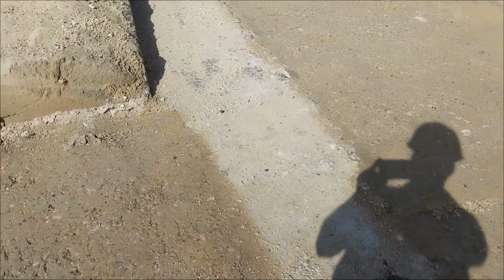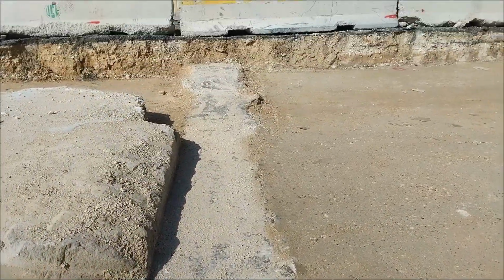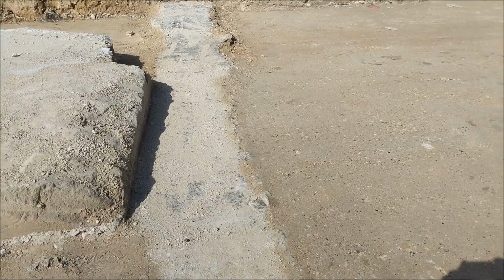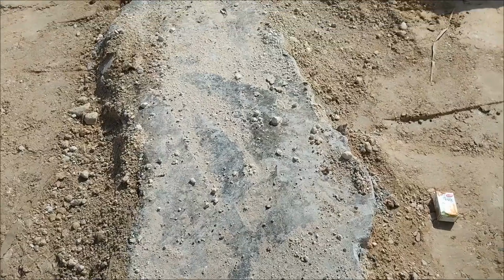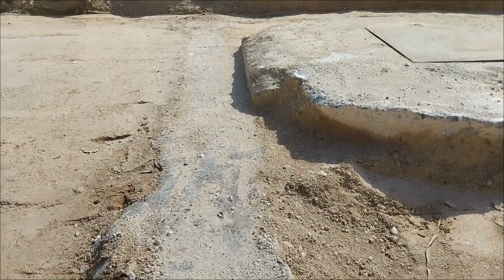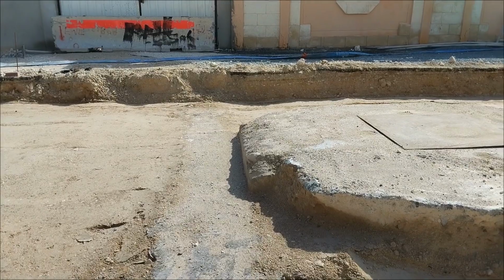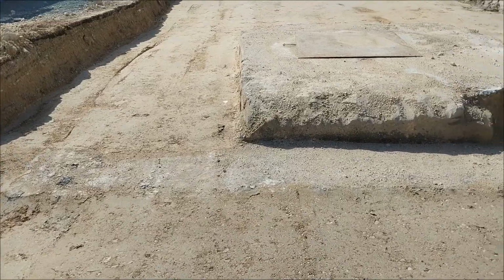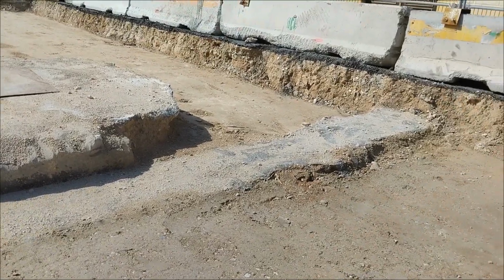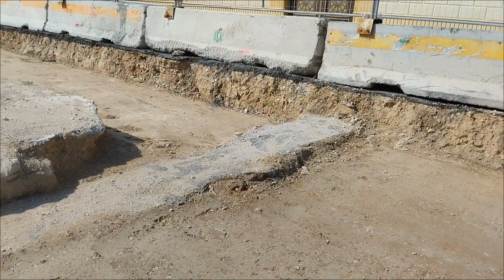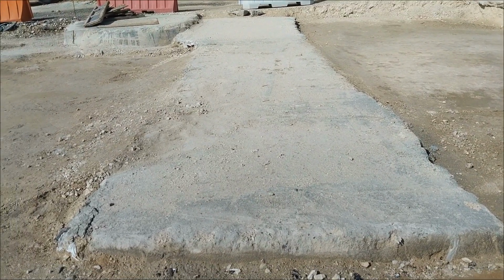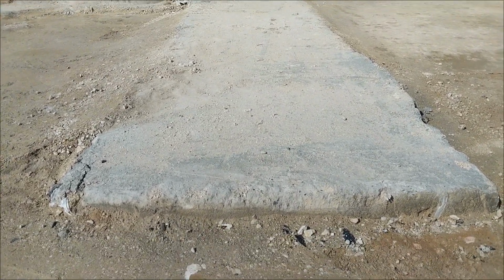As you can see here, this is now on the subgrade bottom level. Sometimes one layer or sometimes two layers come over the concrete ducts, and sometimes it is on the subgrade top level. So at least on the subgrade top level, the duct should be finished, and this should be bitumen coated and warning tape should be installed. As you can see here, this duct is almost completed. It means one layer of the backfill will come here to match the manhole cover level. Then this will be the final subgrade top level.